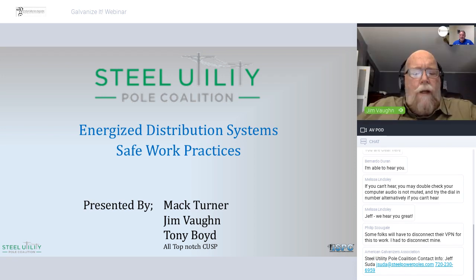I have 47 years in the industry. My first 25 years was with the utility, and then about 10 or 15 years as a contractor also. As Tony goes through the slides, I'll pop in once in a while and we'll talk about some of the things contractors do to work around steel poles, some of the peculiarities, and some of the changes that have happened in the industry as more steel poles have come into practice, especially in setting poles in hot or energized environments, and some of the things we have done as an industry in the field to improve or maximize safety during these installations.